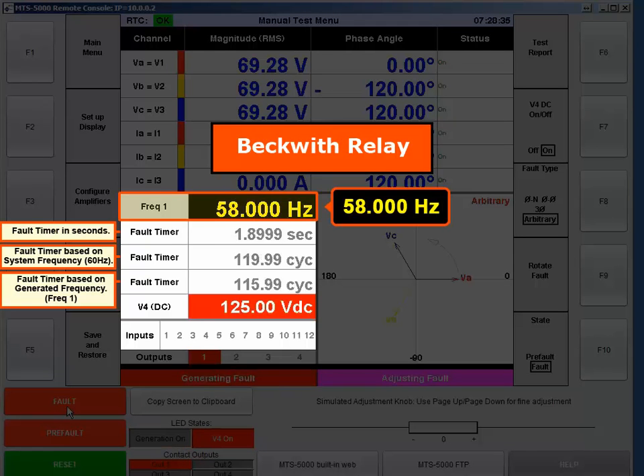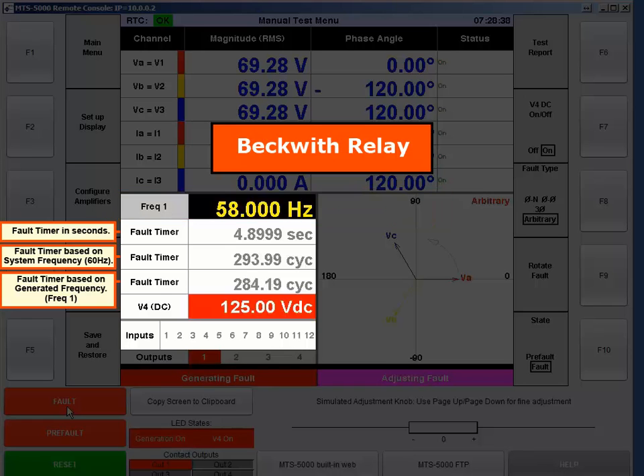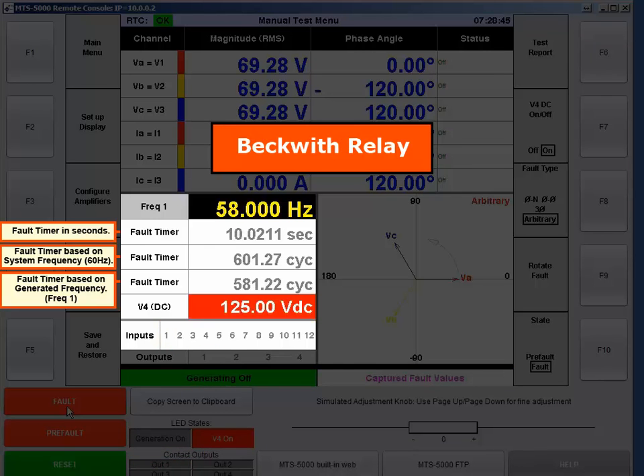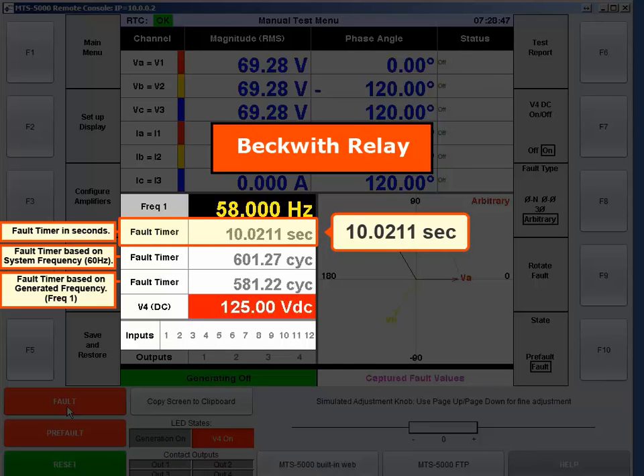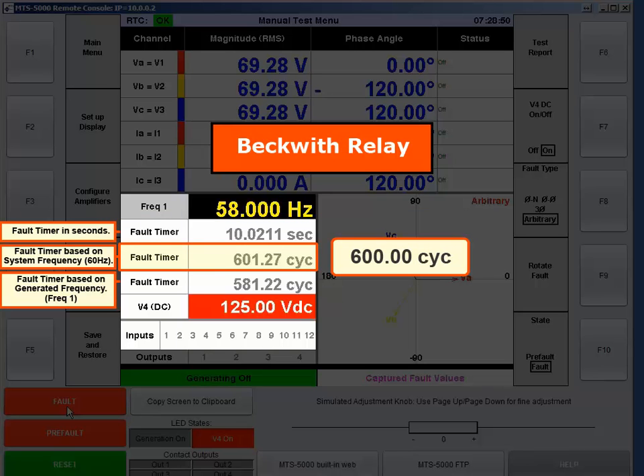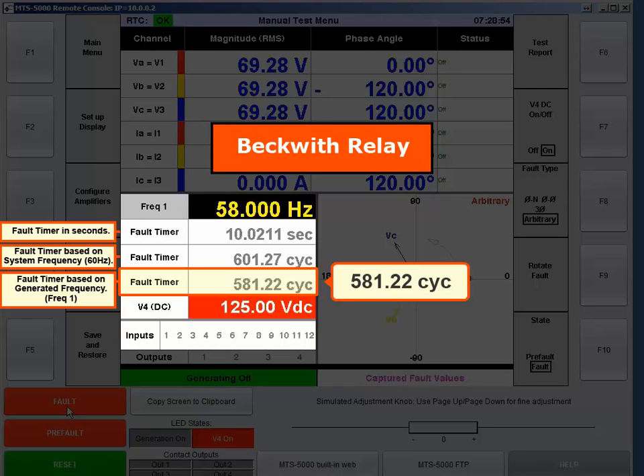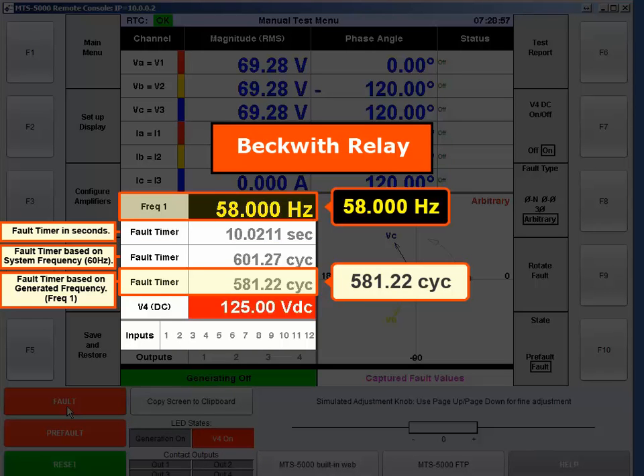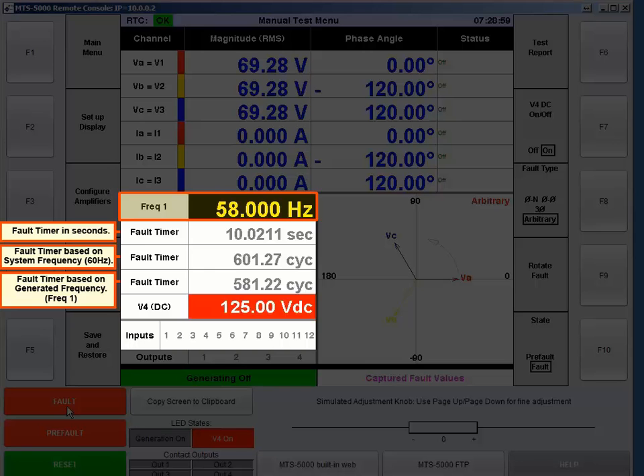I'm going to push the fault button and now the relay is seeing 58 Hz. The trip came in at about 10.02 seconds, which is 600 cycles based on 60 Hz and 581 cycles based on 58 Hz.